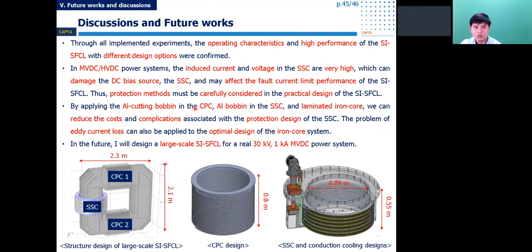Next section is the discussion and future work. Through the experiment implemented, the operating characteristics and high performance of the SFCL with different design options were confirmed. In the MVDC and HVDC power systems, the induced current and voltage in the secondary coil are very high, which can damage the DC bias source and secondary coil and may affect the fault current limiting performance of the SFCL. So the protection method must be carefully considered in the practical design of the SFCL.